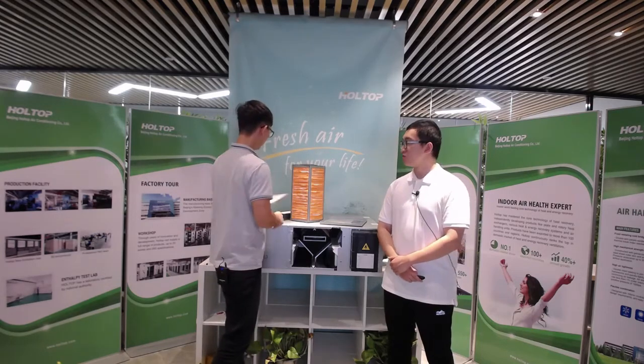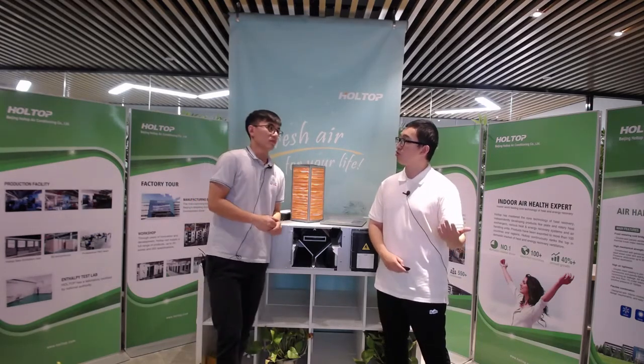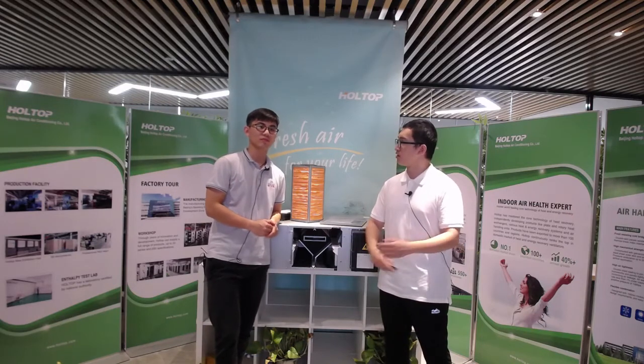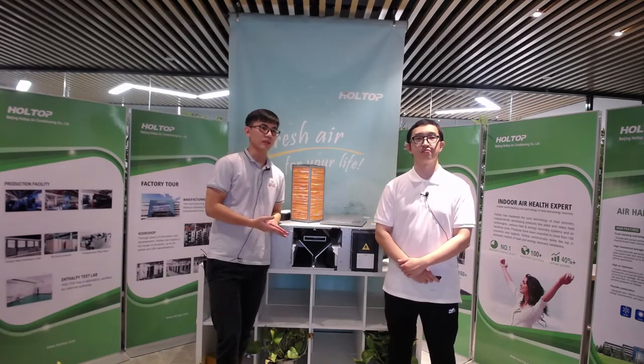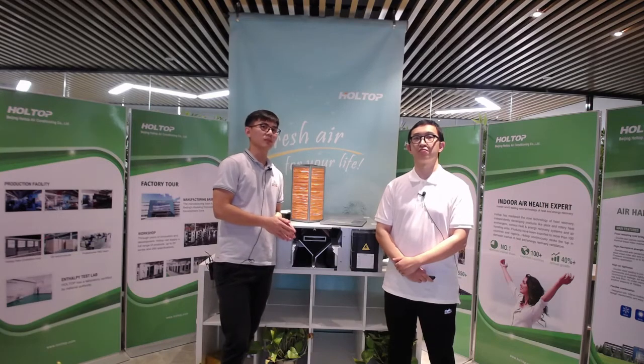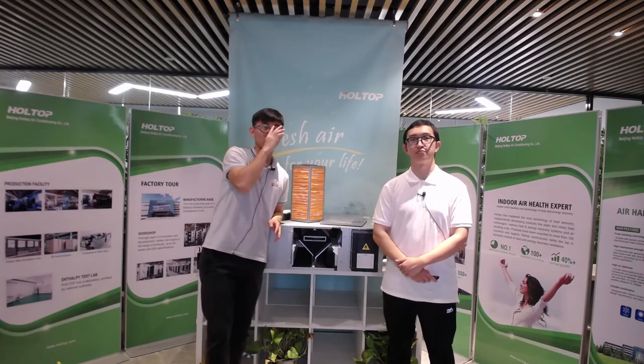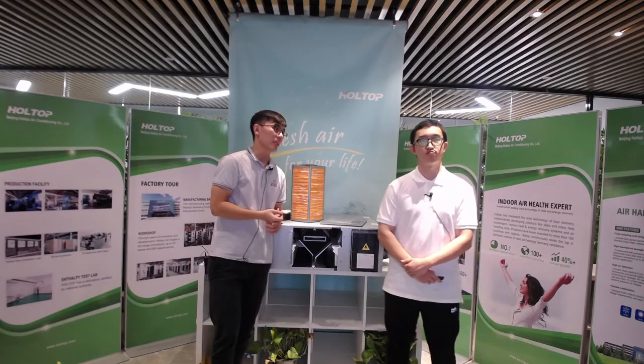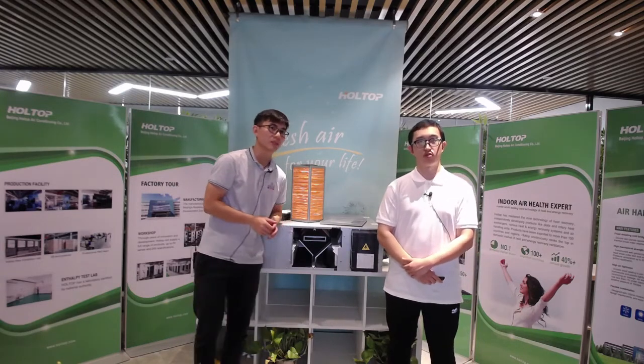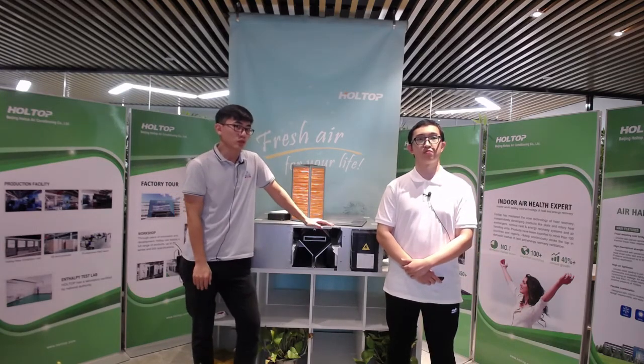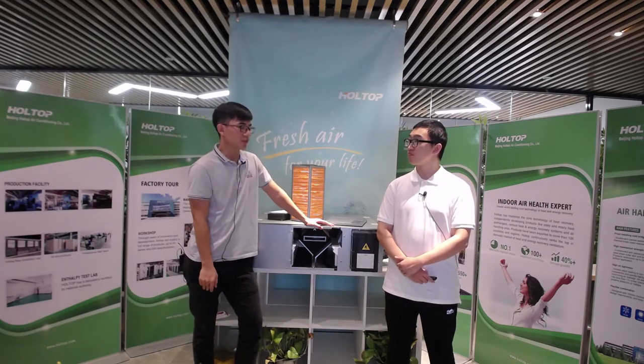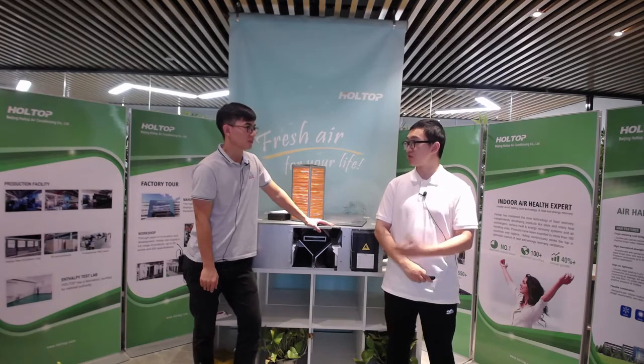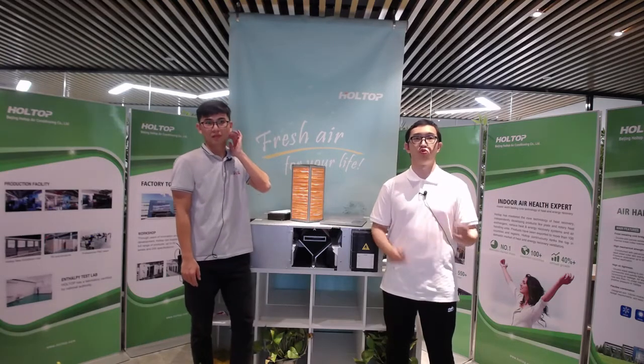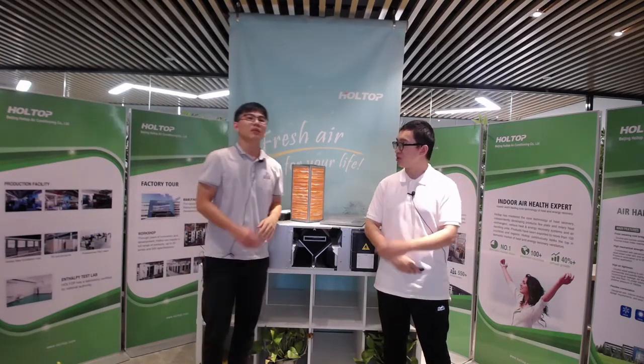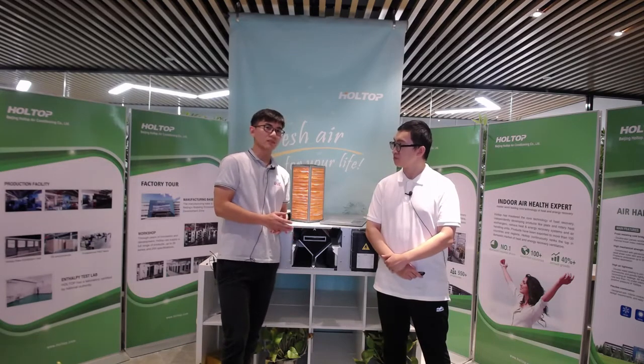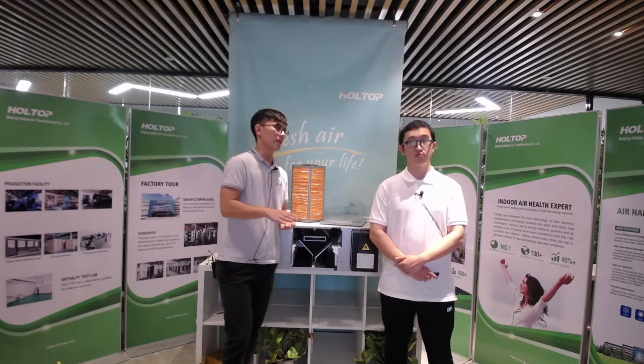So today we're talking about the Ven Pro Plus series. So what's new about it? The main difference will be the external static pressures. Okay. It means that at the same volume, say 800 cubic meter per hour, the external static pressure will be 60 to 70 Pascal higher. Wow, that's a huge difference. So what difference would it make? It will make the airflow stronger under the same ducting system, the same length.